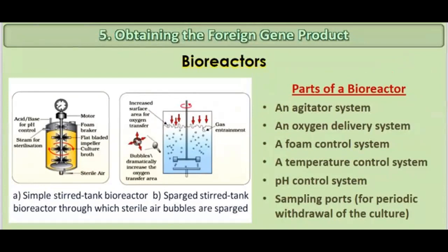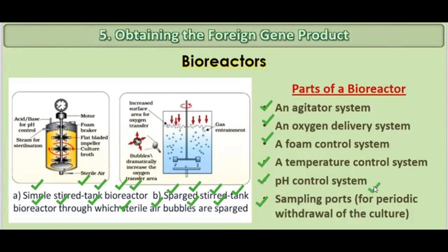The basic parts of the bioreactor include a simple stirred tank bioreactor and a sparged stirred tank bioreactor to which sterile air bubbles are sparged. The parts of the bioreactor are: an agitator system, an oxygen delivery system, a foam control system, a temperature control system, a pH control system, and a sampling port for periodic withdrawal of the culture.